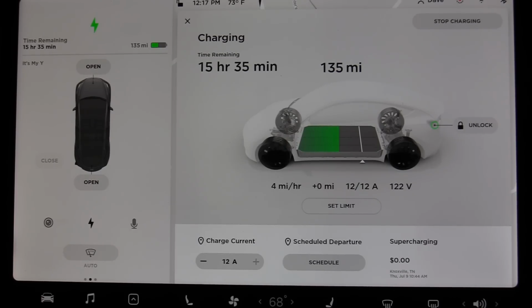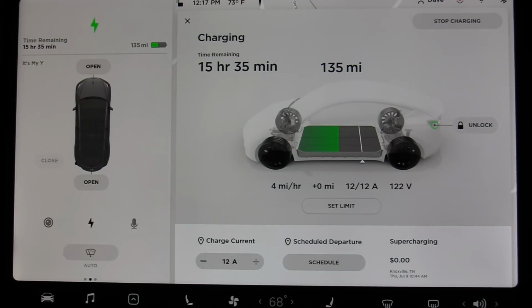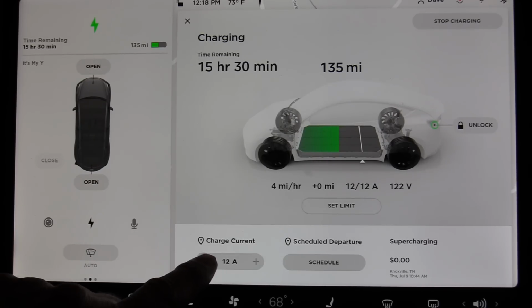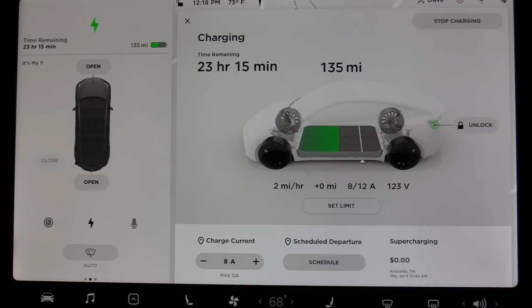Now on the mobile connector, you have a limitation of 12 amps, because being a continuous duty circuit has a limit of 12 amps. But let's say you plug it into a circuit that maybe has some other things connected to it. You can modify the charge current using the charge current selector down to whatever current you want. As you can see, now we're at 2 miles per hour of charge. But if that's all the current you can pull from a given outlet, that's okay—at least you're getting 2 miles per hour of charge.